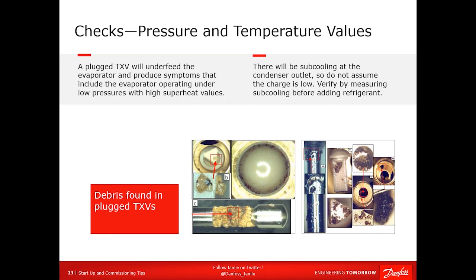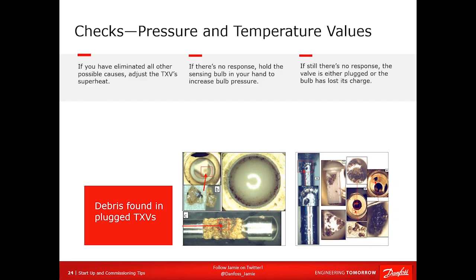Finally, we have the famous copper oxide that comes from brazing copper with no nitrogen. Now, I'm going to tell you why you should always use nitrogen, aside from the fact that it stops this from happening, because it's a real time saver. But we're going to get to that in a minute. Suffice it to say, if the TXV is plugged and you have solid liquid at the TXV, now you've got an issue. All right. Try adjusting the superheat.